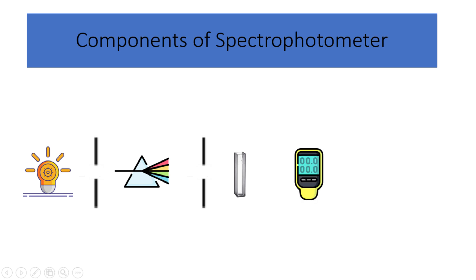Detector. The detector captures the light that has interacted with the sample and converts it into an electrical signal. The electrical signal generated by the detector is proportional to the intensity of light at a specific wavelength. Signal processor. The electrical signal from the detector is processed by a signal processor, which amplifies, filters, and digitizes the signal.